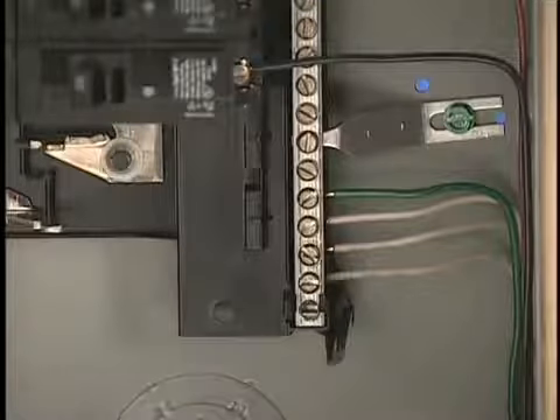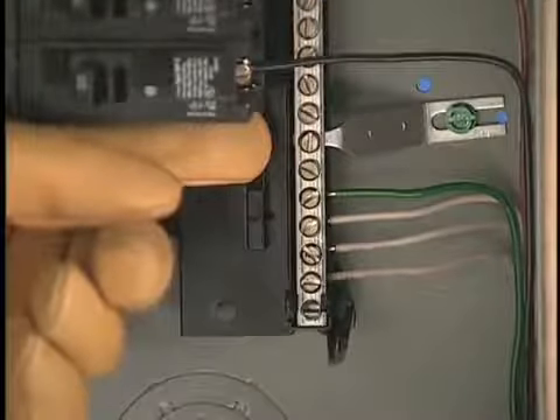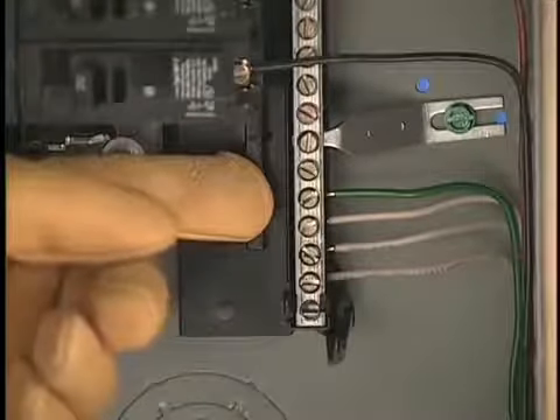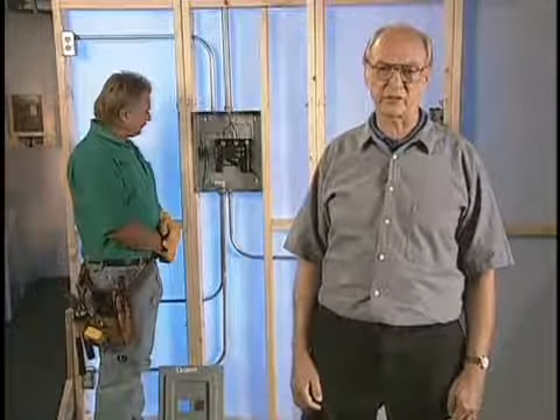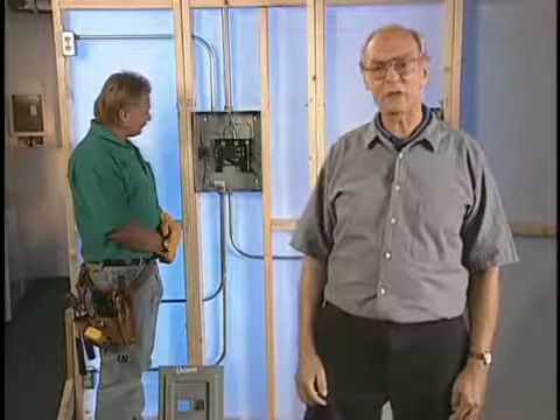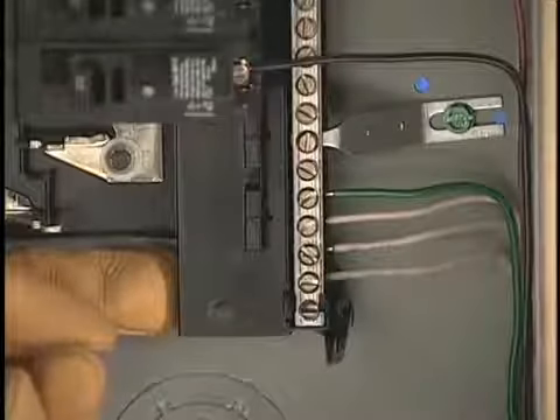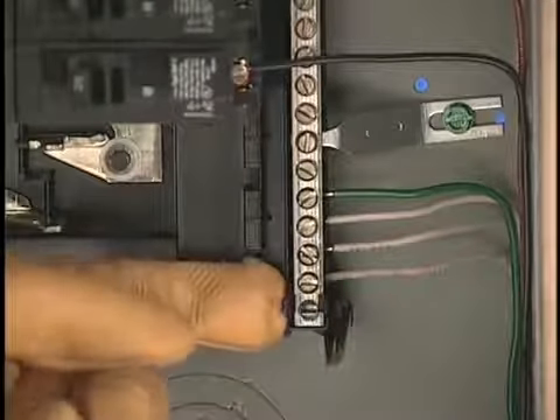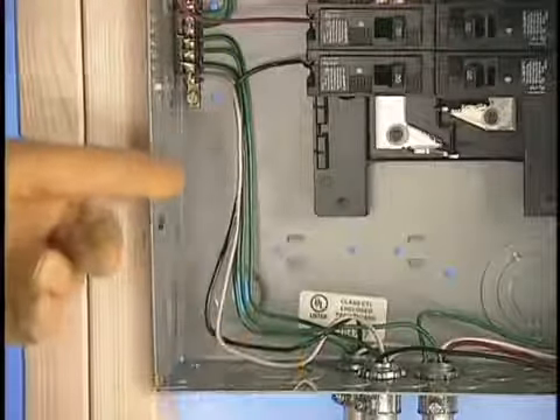The first is when a neutral bus is bonded to the subpanel, or there are equipment grounds connected to the neutral bus. Here we're using a simplified demonstration panel to illustrate various misconnections. The consequences of this situation are currents on various metallic structures in the building, as well as a net current on the panel feed all the way back to the service entrance point. The neutral bus must remain insulated from the panel and the bonding screw either turned out or removed. It's only there in case the panel were to be used as service entrance equipment. Also, check to see that no neutral is connected to the grounding bus.